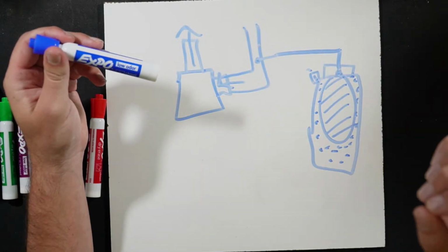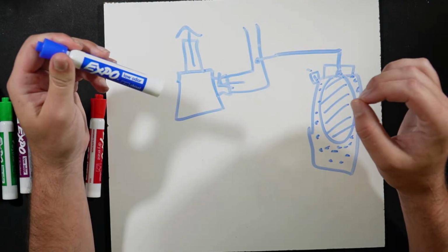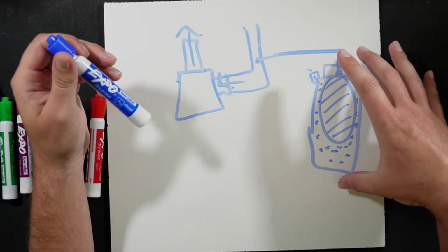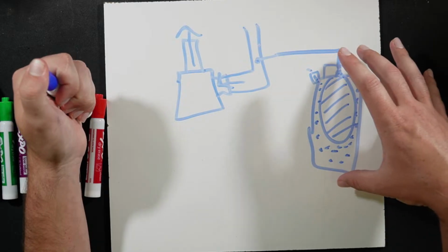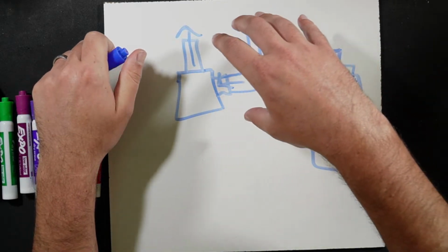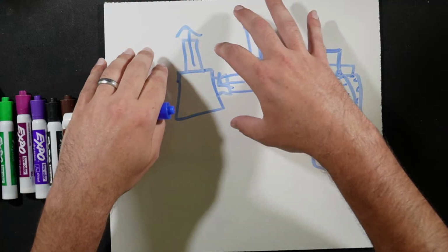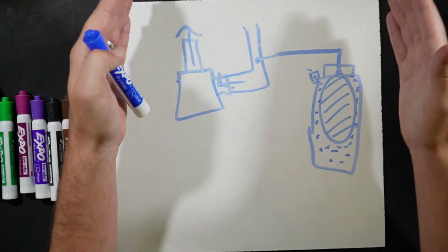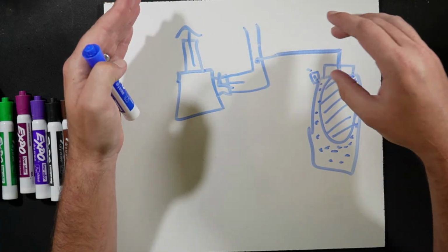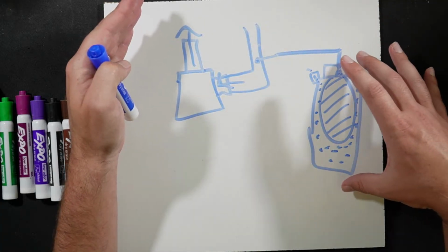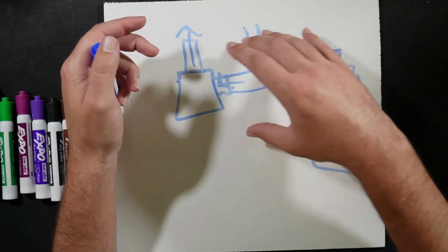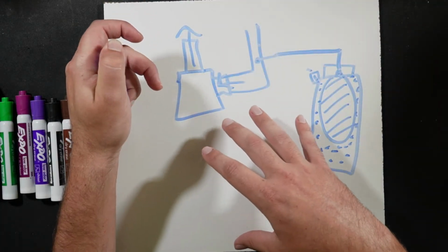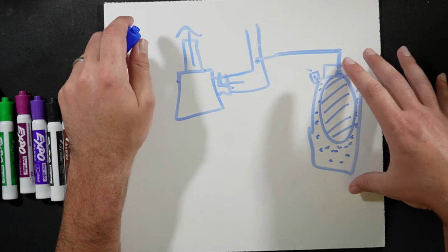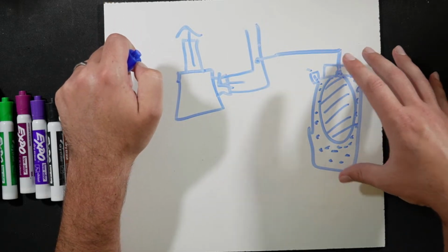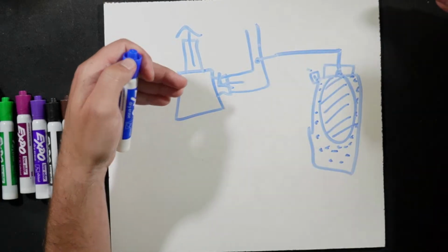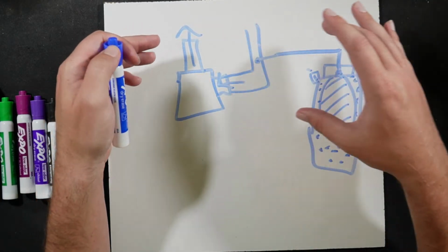Now, in most plants, I see that they try to put these at the top of the loop. Sometimes that means if the whole plant and pump assembly are at the top of the loop, then the whole thing will just be up there together, in one piece. There have also been cases where they'll put this at the top of the loop, but the plant and the pumps will be down at the bottom of the loop. So these are not always located with the pumps. Sometimes they'll be separate at the top, and sometimes they may be down close to the pumps.